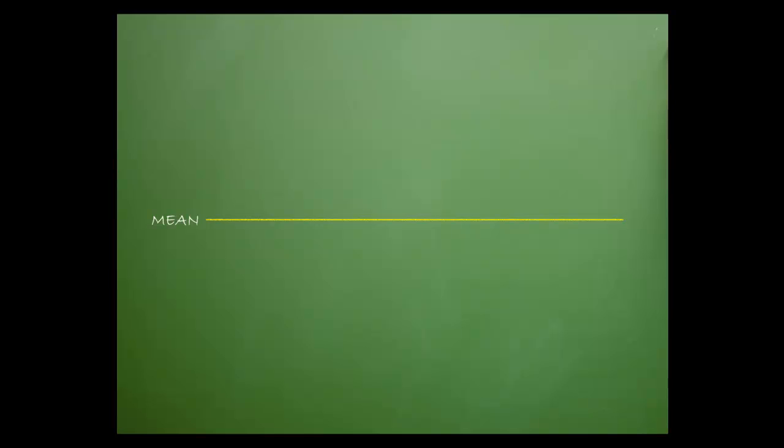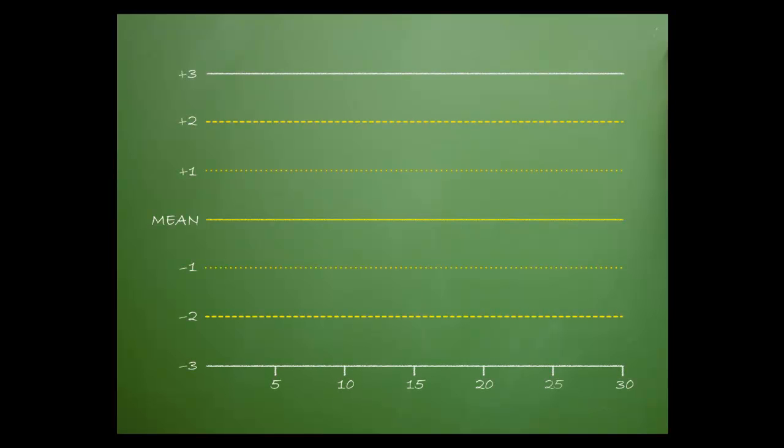To build an LJ chart we start with the mean of our control data. The next step is to calculate the standard deviation. We now have the framework for our LJ chart.